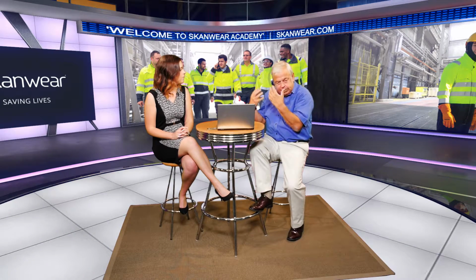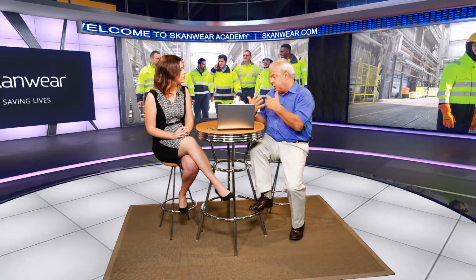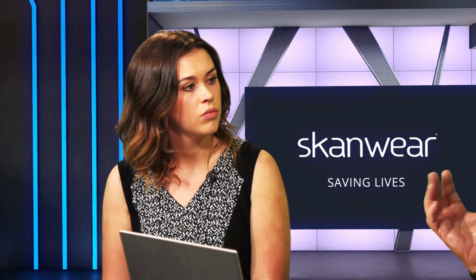Part of the blast, when the plasma ball comes out, it consists of vaporized copper, and copper expands at 67,000 times its own volume. On top of that, you get shrapnel, bolt heads, and anything else blown out of the cubicle. And the big thing about the copper vapor, if you're not wearing your face shield - and this is an accident I investigated not so long ago - your face will get copper plated, and your hands too if you're not wearing gloves.